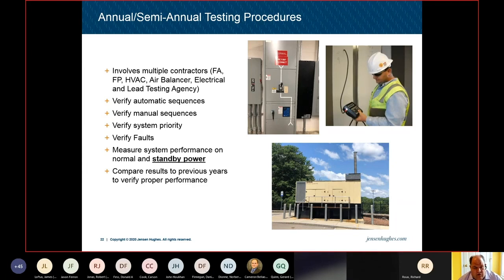The smoke control systems are sacrificial. They kind of run. There's not really safety interlocks that stop them from running per se. So we need to verify those priorities are in place, and that there's not things that are going to stop the smoke control system from running when we really want them to be running. We also need to verify faults, so we test every single light on that panel. The green light on is on, off is off, open is open, closed is closed. And we need to get positive confirmation in the field that we're reporting back the right information.